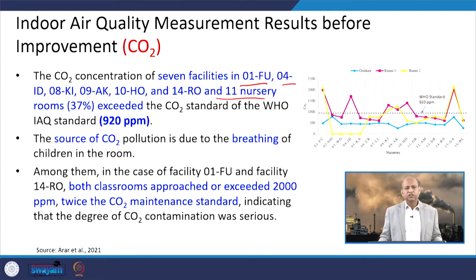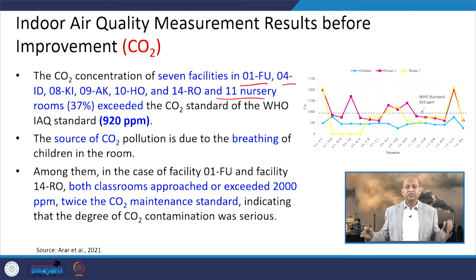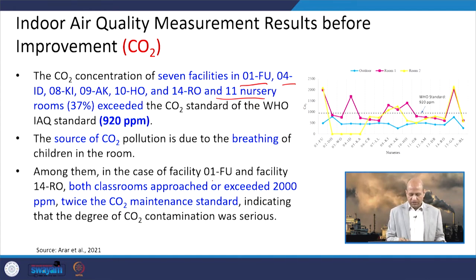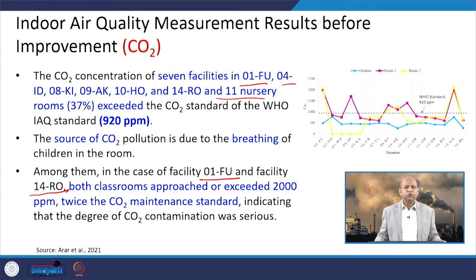When we inhale, we consume oxygen; when we exhale, we release CO2. That CO2 builds up in concentration if there is no proper ventilation. Among the facilities, 01fu and 14ro both approached around 2000 ppm — more than twice the prescribed standard — which is a very serious issue, as those rooms would cause significant suffocation and create a poor environment for children's learning and play.